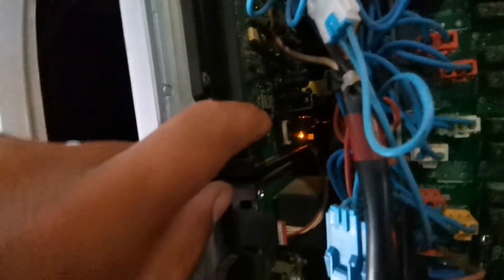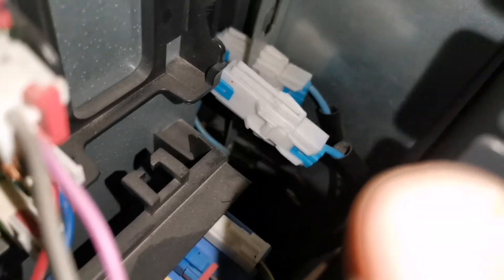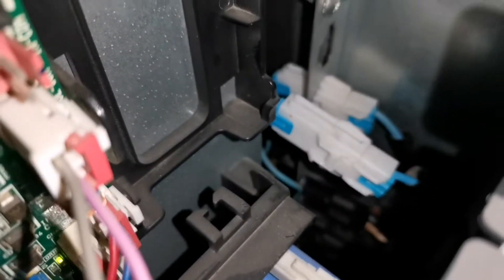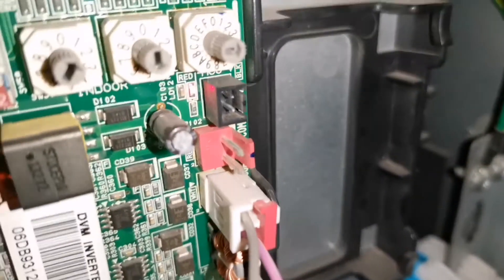We should have a green light flashing on the inverter board but we do not. We need to check if we're getting three-phase to this inverter board. The reason we had that 206 C004 error was because that contact at the bottom - the spades on the inside pushed to the back - so it wasn't making proper contact. On that one inverter board we weren't getting proper three-phase power.